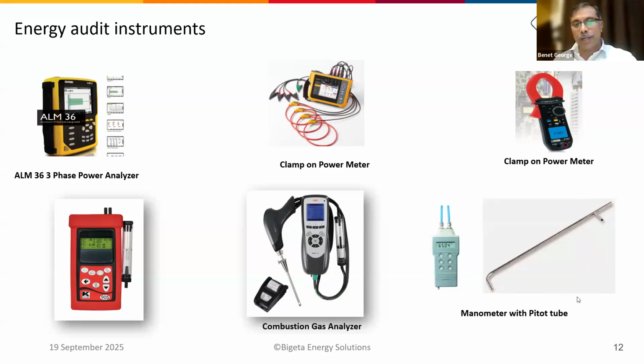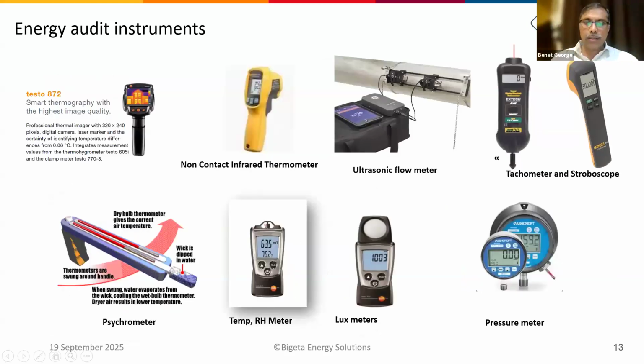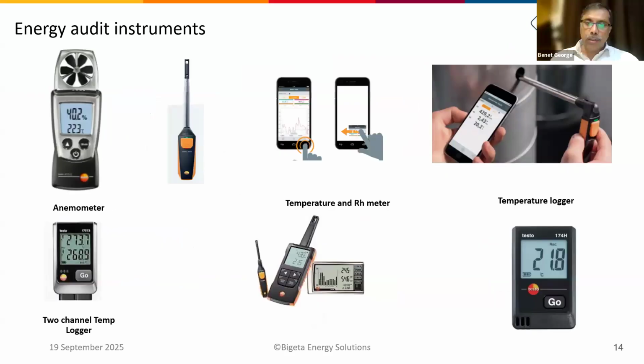The second is the clamp-on meter. It can typically be used for constant load conditions. Say, for example, you have a pump. Typically, it is almost constant, so you can take an instantaneous measurement. Some of these instruments are a flue gas analyzer to check the flue gas, and a pitot tube and manometer for air velocity, airflow and air pressure. The thermal imager can be used for hotspots, and the non-contact thermometer is also used for measuring temperature. Others include an ultrasonic flow meter for water flow measurement, stroboscope, temperature data logger, lux meters, pressure meters, anemometers, and temperature and humidity meters. These are some of the instruments used in an energy audit, or in a detailed energy audit.